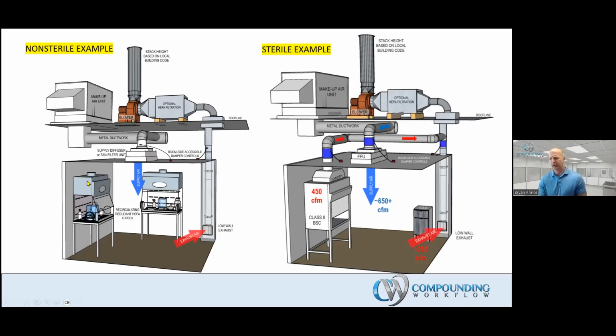I like room neutral hoods because these are not externally exhausted. They are what we call room neutral. They do not contribute to the negative pressure and they do not contribute to the air changes per hour in this non-sterile situation. So I'm using a low wall exhaust so that I can sweep the air and balance this space. Now, many years ago, I used to be in the engineered containment business, and that's a fancy name for hoods, really. And I can tell you, the more hoods you start connecting externally to an exhaust system, the more of a Rubik's Cube it becomes. So USP 797 used to have a parameter of 0.02 to 0.05 positive.